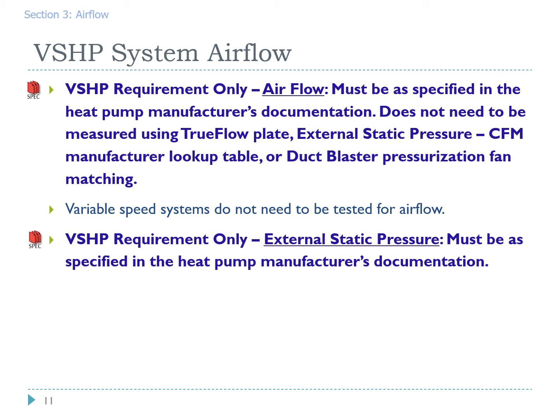Variable speed heat pump system airflow. The airflow of a variable speed heat pump does not need to be tested, but the installer must confirm that the airflow meets a manufacturer specification. By variable speed, we mean a heat pump system that has an inverter-driven compressor. For variable speed systems, the technician must also supply the maximum external static pressure that's allowed by the manufacturer.